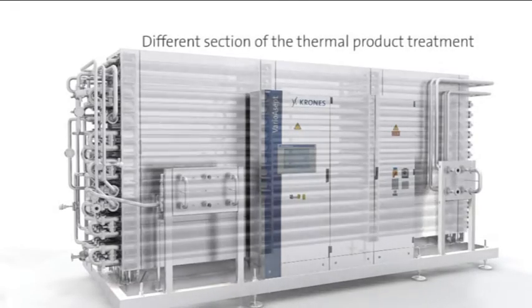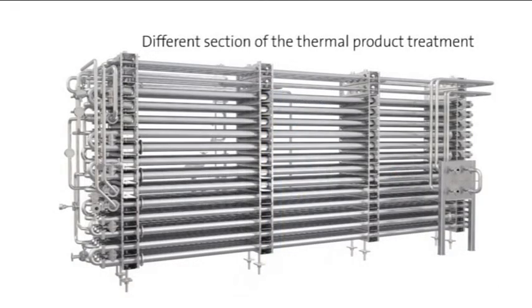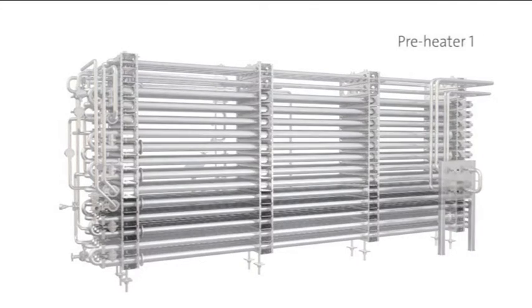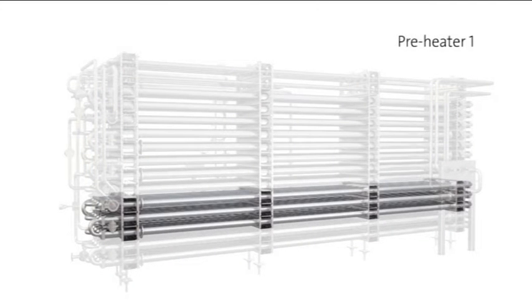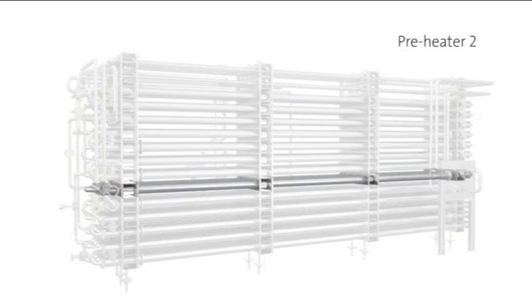Now we come to the different sections of the tubular heat exchanger for thermal product treatment. We start with the first pre-warming zone, which is regenerative in design. An indirect water circulation feature on the secondary side of the heater warms up the product with maximized energy economy.